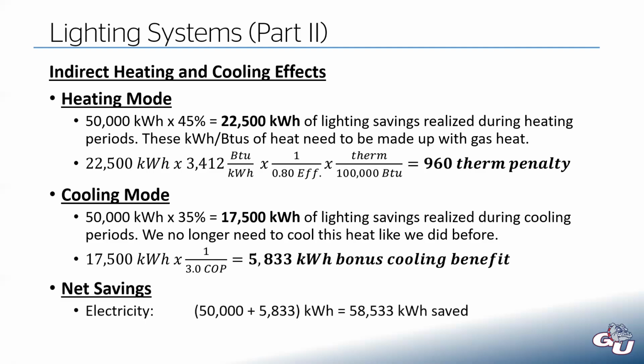On the electricity side, we have our lighting savings, just based on the before and after wattages of the light fixtures. We have this cooling bonus. So we gained a little over 10% on our electric savings. And now we arrive at about 58,000 kilowatt hours saved after accounting for the air conditioning savings. But on the gas side, well, we saved more on the electricity side, but now we have to spend more in gas. So we've increased our gas bill by 960 therms. So that will be a financial hit on the gas side.